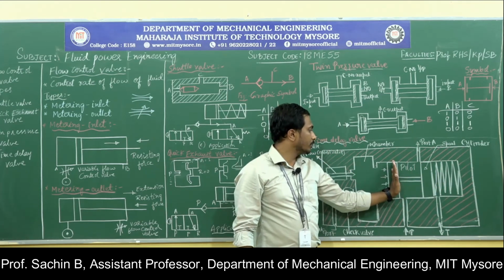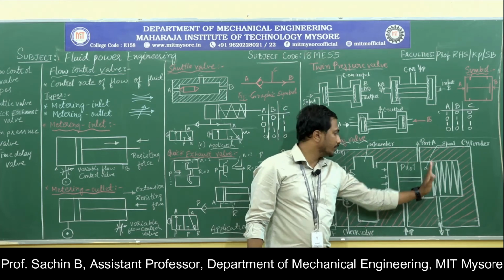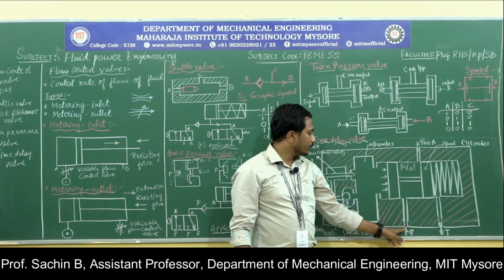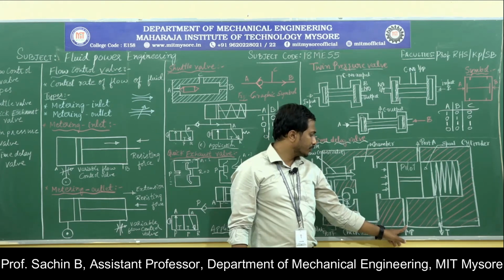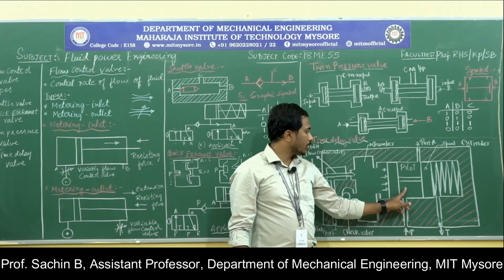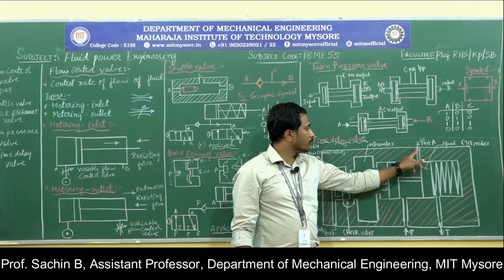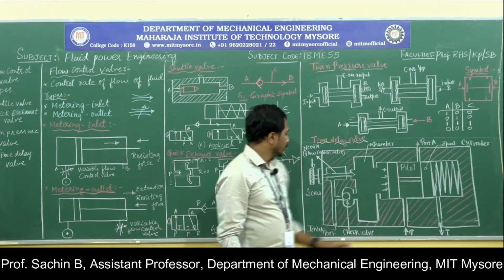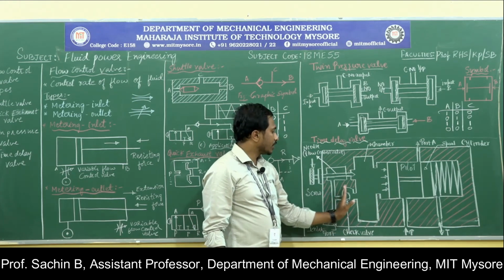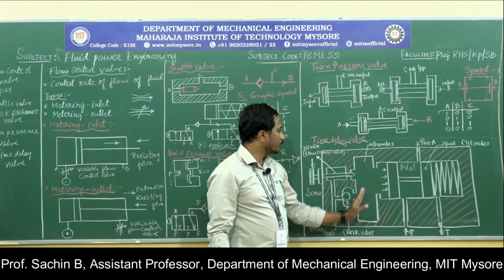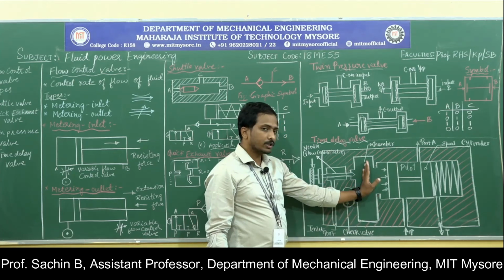Means the pilot movement, or the spool movement, will be there, due to which the compressed air that is already connected to this port will allow the flow of fluid to port A. Means with the help of the inlet port I am supplying the compressed air. The check valve will allow the fluid through, and it will get stored here.